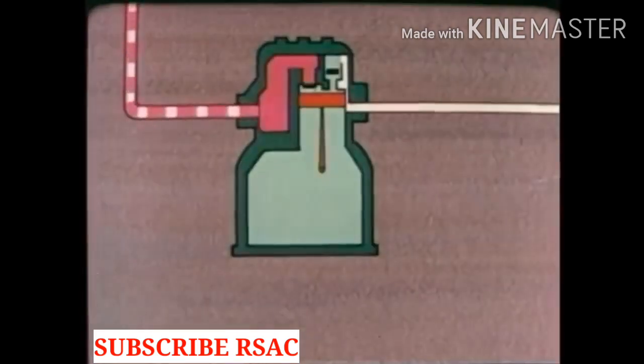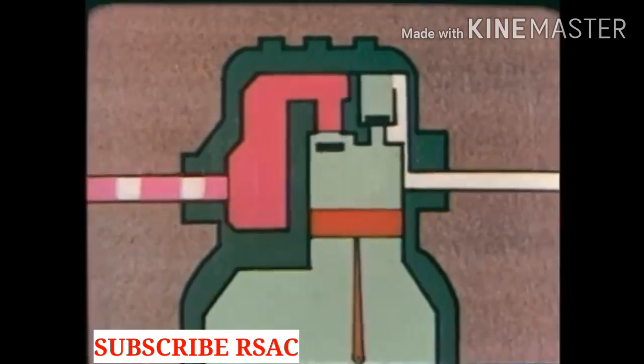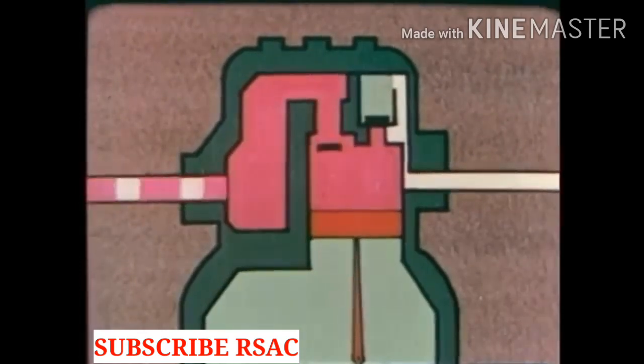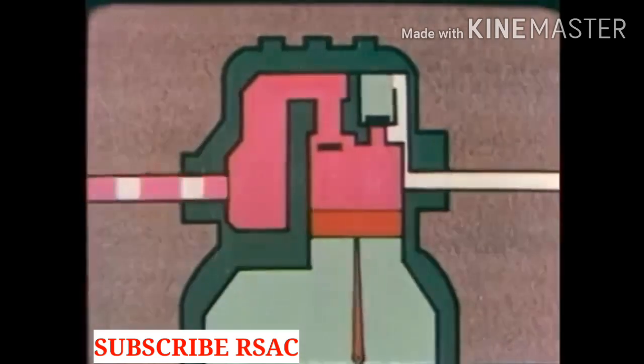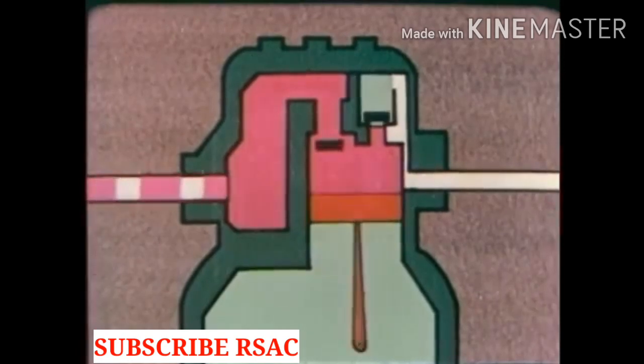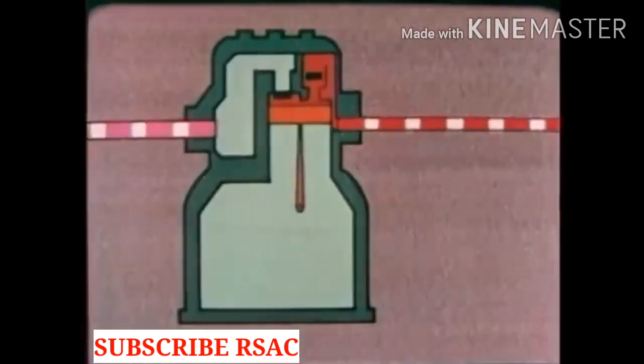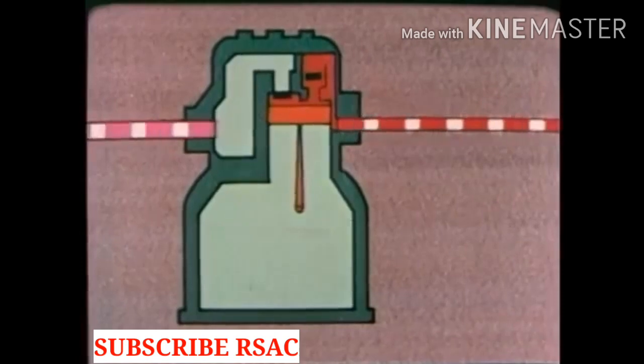The gas is sucked through the connecting line into the compressor. As the piston moves down the suction valve opens. The gas is sucked into the compressor. As the piston starts up again the suction valve is forced shut and the discharge valve is pushed open. On this stroke the gas is compressed. Remember what happens when gas is compressed: pressure goes up, temperature goes up. The gas now at high pressure and high temperature flows into the condenser.